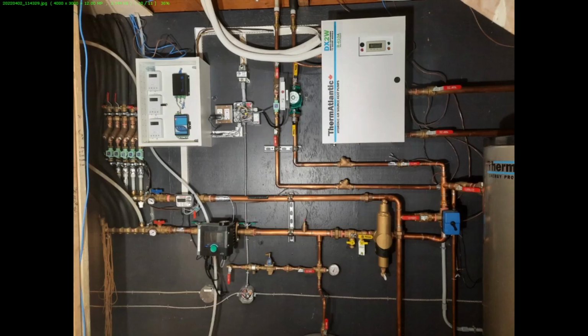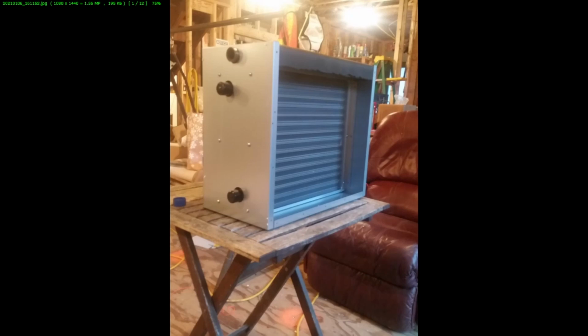So going back to the system, this is prior to it totally being finished. Not all the sensors are installed at this point. Not all the wiring is complete. But basically, we've got our iNet, we've got our hub, we've got 3 of our iStats that are, as I said, BTU monitoring and extra control. We've got our DX2W, got the relay that is controlling the circuit that's going to the air intake of the HRV, and I've got a coil in that intake, and this allows for the preconditioning of air into the HRV.